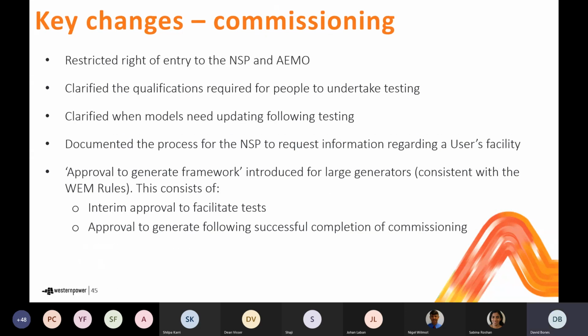We also, as I mentioned earlier, introduced a few changes to the remainder of Chapter 4. These mainly touch on things like commissioning, inspection and testing. Some of those revisions highlighted on this slide include that we've suggested restricting the rights to inspect facilities to just the NSP and AEMO. The current drafting is a bit more open and could be interpreted as allowing that right of inspection to be much broader. We believe that's probably unintended, and so it's appropriate to tighten it up.